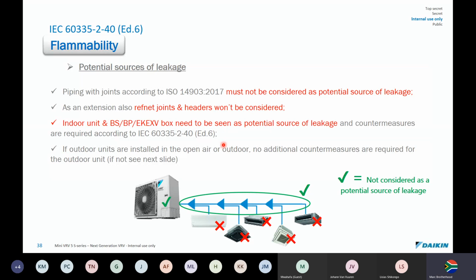So the standard that Daikin used describes potential sources of leakage. They define them. So the standard says piping with joints must not be considered as a potential source of a leak. As an extension, also ref nets and headers won't be considered. So the standard does not consider ref net joints potential leak sources, as well as piping. The standard also says indoor units, which is BS boxes, EKEXV boxes, need to be seen as potential sources of leaks and countermeasures are required. So in a nutshell, ref nets are excluded.